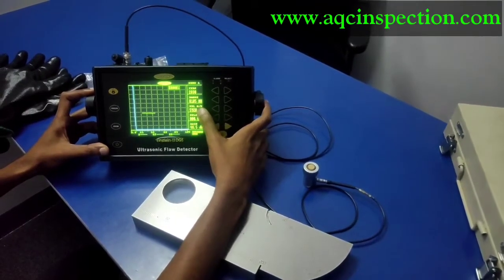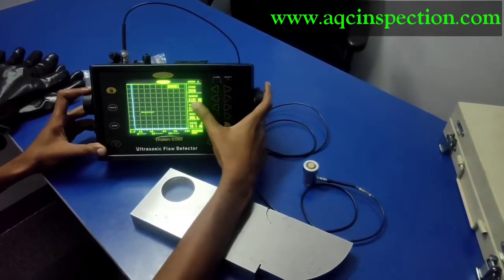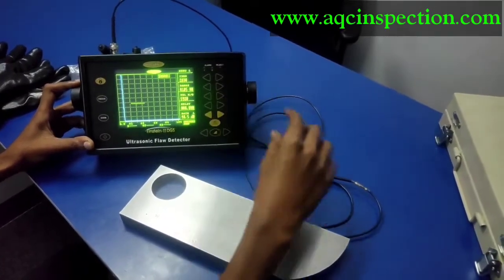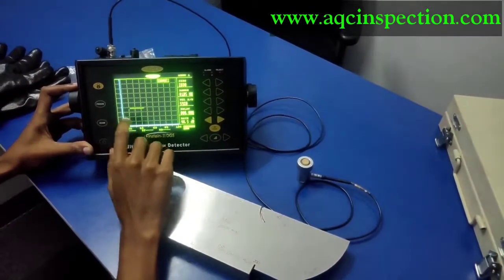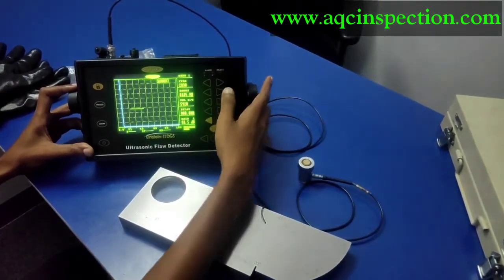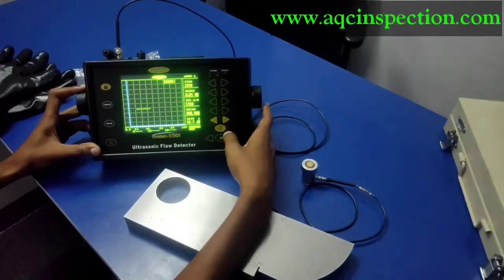This is the velocity for steel which is 5900 m/s. Then the range I have set is 105 mm because I am going to set four backwall echoes which is 25, 50, 75 and 100. So I have just put 105 mm instead of 100 so that I can see the backwall clearly.